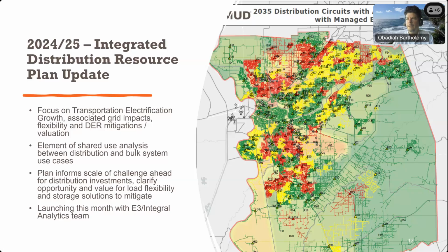When we dug into this from a purely EV perspective, most recently, we found looking out to 2040, in order to serve about 50% more energy, which is anticipated for demand for electrification by 2040, we would need to upgrade something like 40% of the substations on our system at a cost of over $1 billion above our baseline cost. And managed charging was able to cut that about in half, but still that's really a massive investment for us.